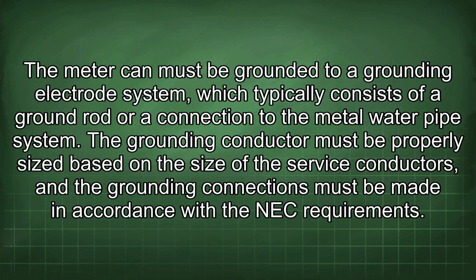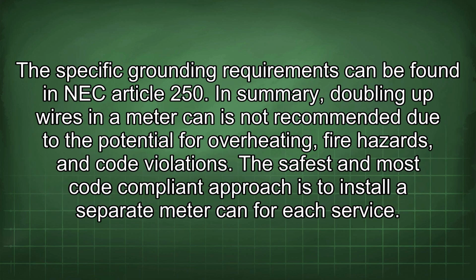The meter can must be grounded to a grounding electrode system, which typically consists of a ground rod or a connection to the metal water pipe system. The grounding conductor must be properly sized based on the size of the service conductors, and the grounding connections must be made in accordance with the NEC requirements. The specific grounding requirements can be found in NEC Article 250.